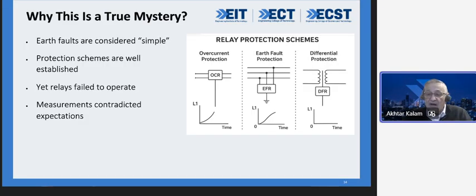The second concept that I want to talk about is the failure to operate. That means your relay has misoperated. There could be errors in logic and design. There could be settings which are inconsistent. You have done commissioning which is wrong. Contact failures, especially if it's an electromagnetic relay, can be a problem. The DC system could be at fault. All that can happen in the relay itself.